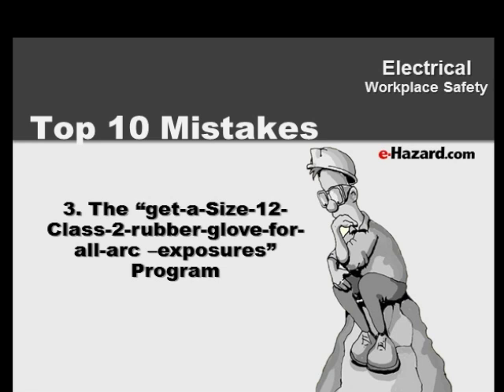The second thing that happened was they said, okay, what's the maximum voltage we could work on? And someone said, well, we got 4160, which they actually never worked on. He said, okay, great, let's go the next notch up, which will be a Class 2 glove, 17,000-volt glove. The first time anybody tried to land a control wire in that 17,000-volt glove, it was impossible. So basically the workers, because nobody was auditing, nobody was checking, they didn't wear it. And then the second thing was they had a flash suit. It was a 100-cal flash suit because they bought the biggest, best kit. That's what they assumed.